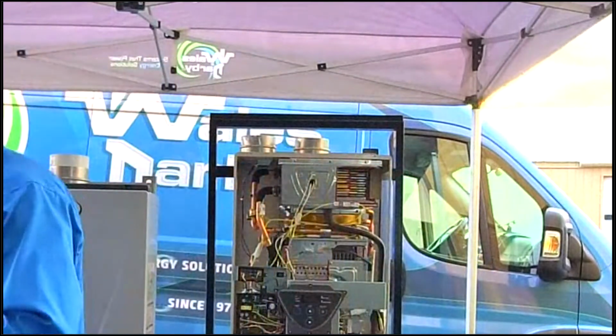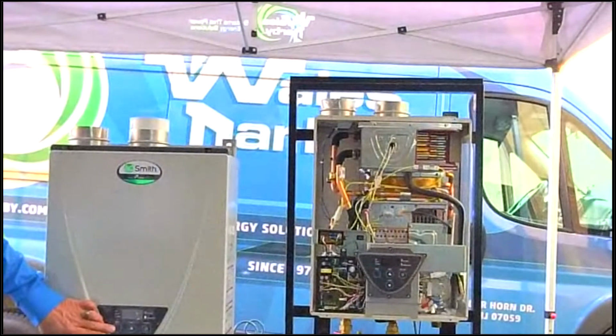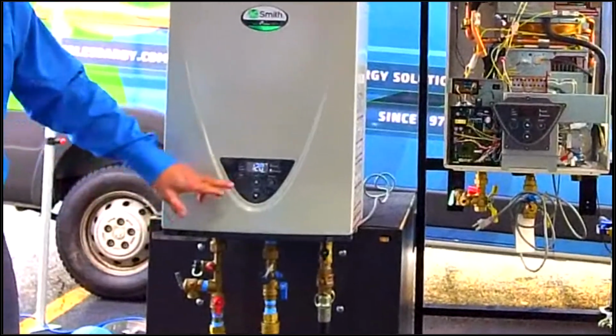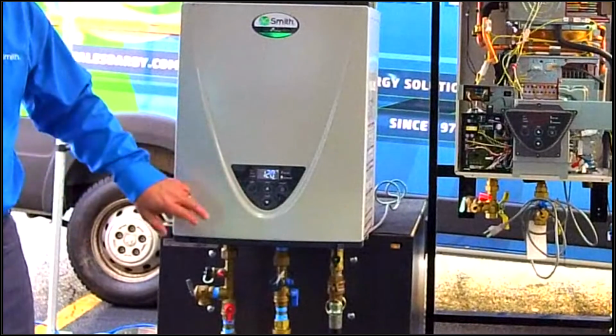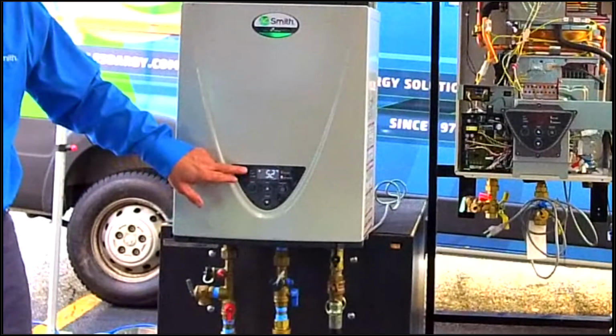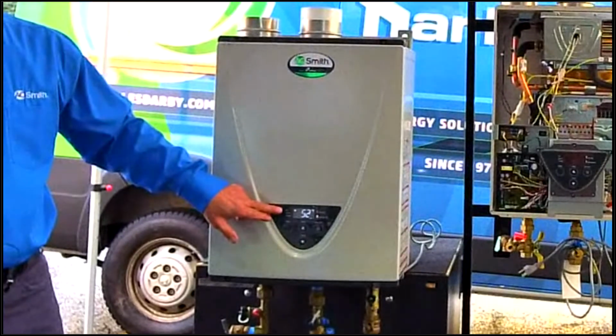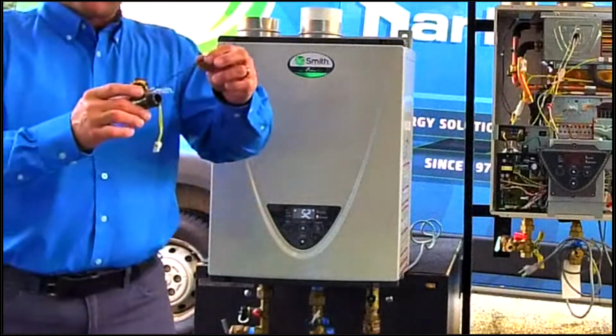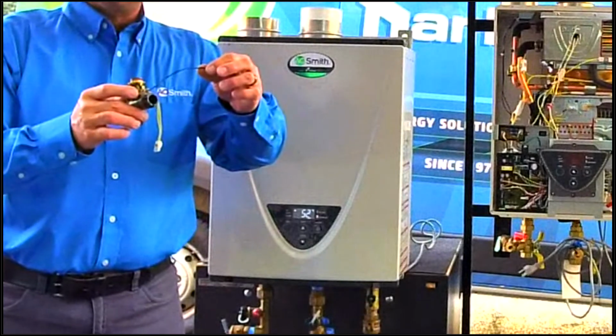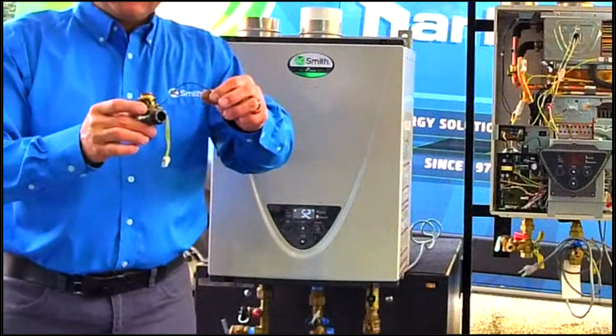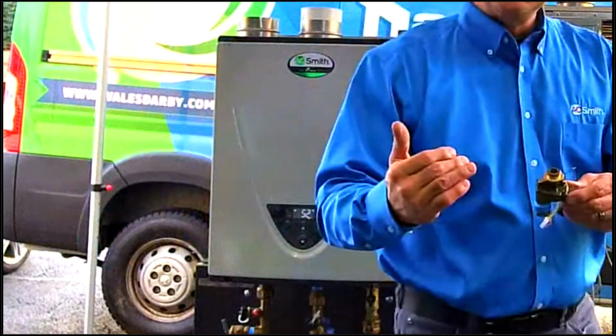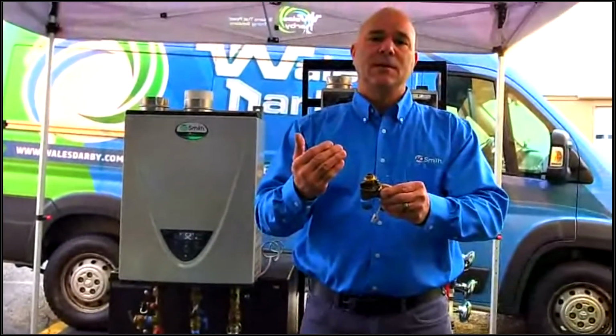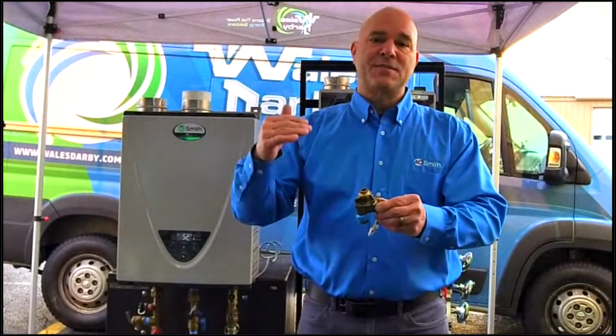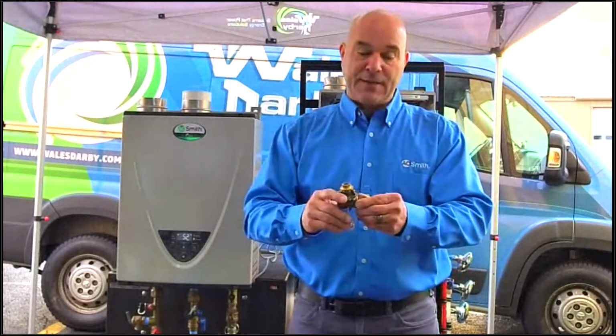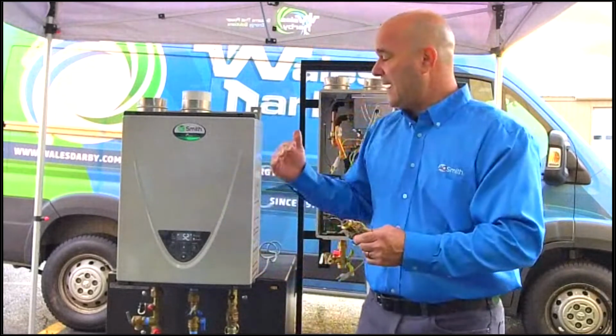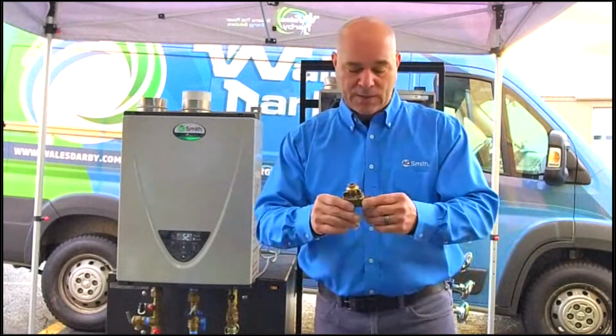If I go to this control and push this information button, that's my target temperature of 120. If I push it again, you'll see a little arrow go right here. It says 52 degrees. This thermistor wire right here is what's sensing 52 degrees. So the unit knows the temperature of the water entering. It will fire and match the demand that it needs based upon the inlet water temperature and the exiting water temperature, our target temperature of 120.